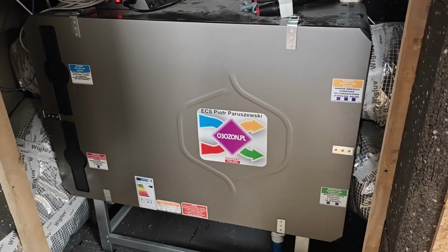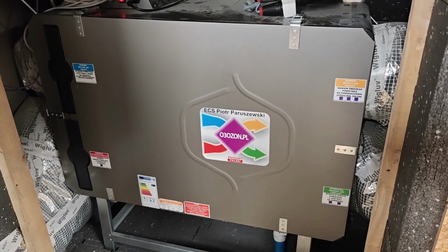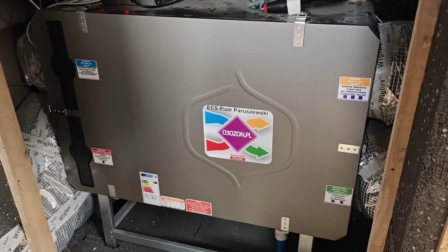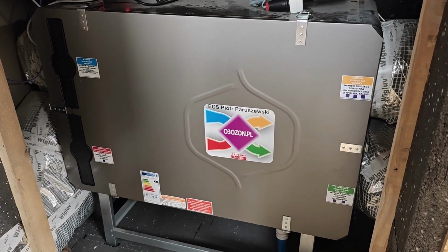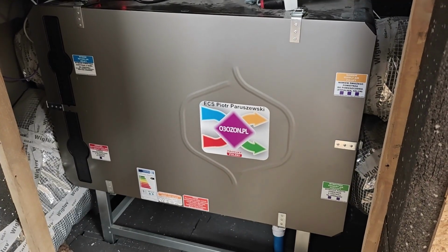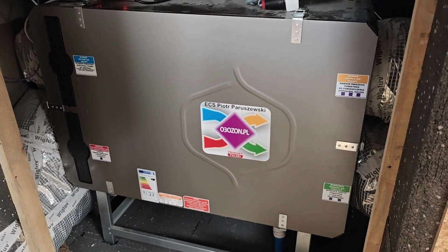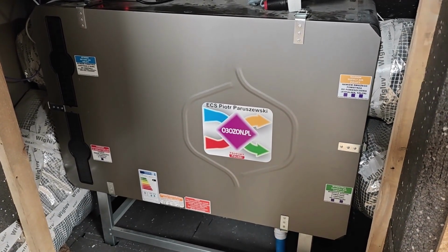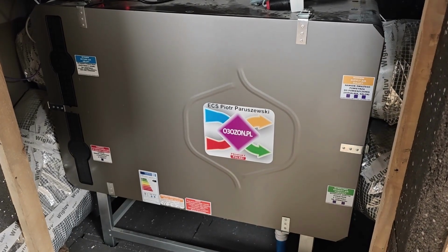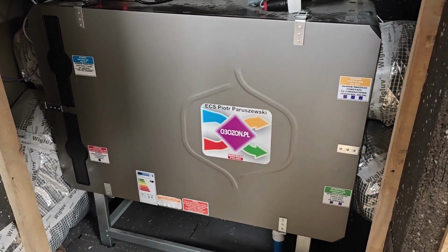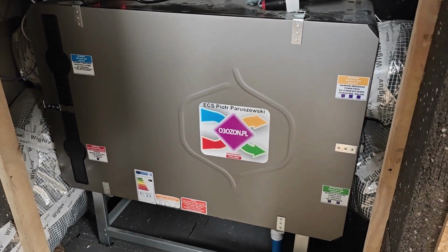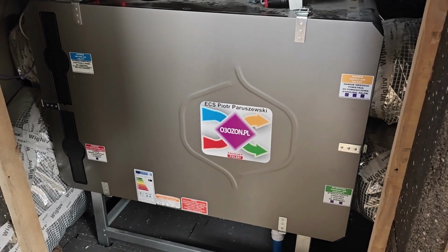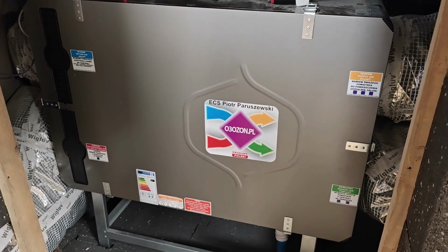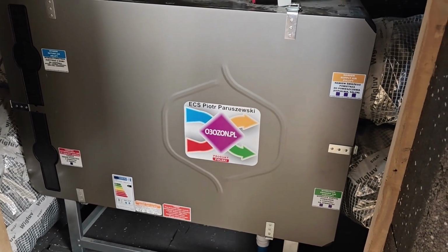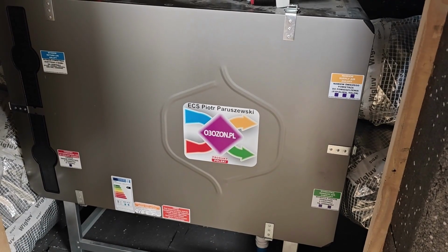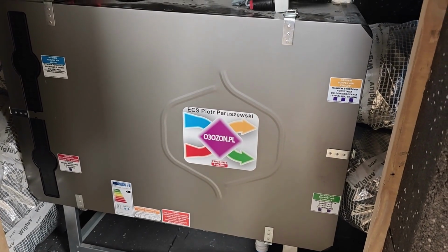The next part of the system, or rather its heart, is the recuperator. In my case, I'm using a CWK 450/200 Eco unit. The heat recovery unit is oversized and the nominal airflow for the building is achieved when the fans operate at 45% of their capacity. It is equipped with an automatic bypass system, which proves to be extremely useful, especially when working in conjunction with the ground heat exchanger. The air cooled by the glycol solution goes directly into the house and it is not unnecessarily reheated by the exhaust air. The situation is quite similar during the nighttime hours as well.